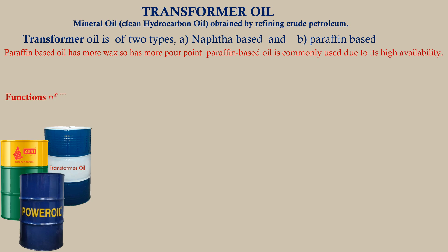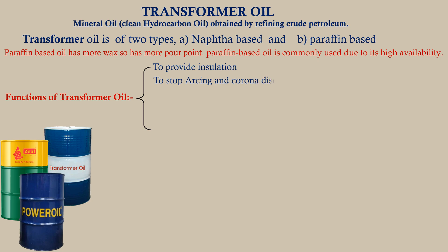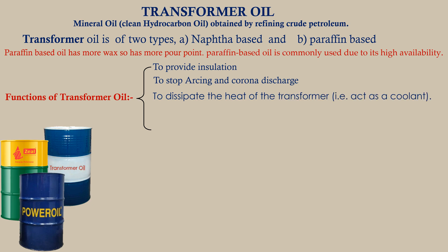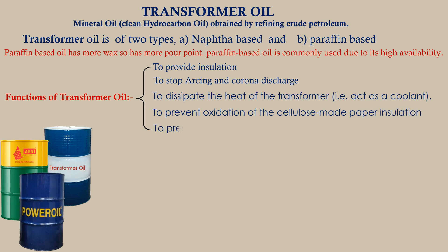Functions of transformer oil: to provide insulation; to stop arcing and corona discharge; to dissipate the heat of the transformer, i.e., act as a coolant; to prevent oxidation of the cellulose-made paper insulation; and to preserve the transformer core and windings.